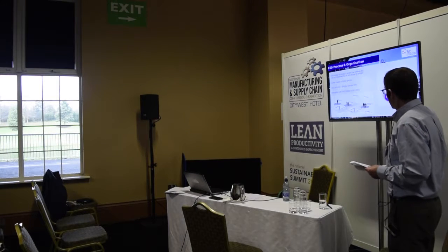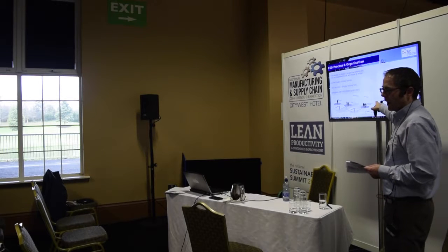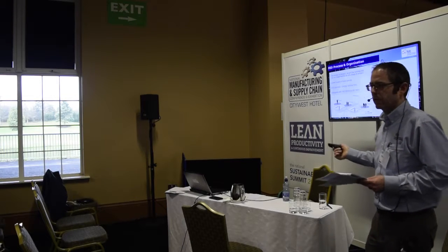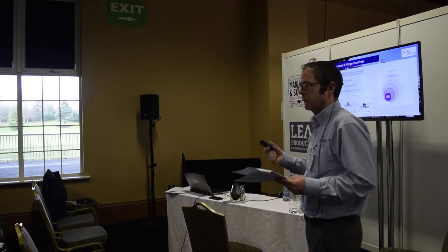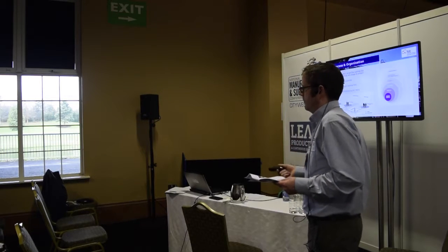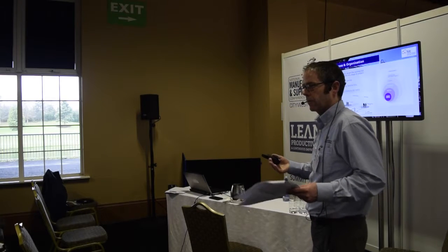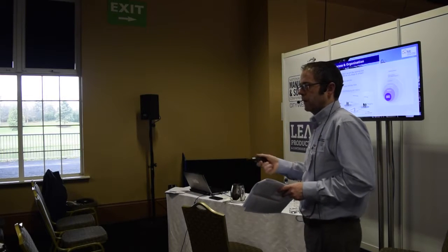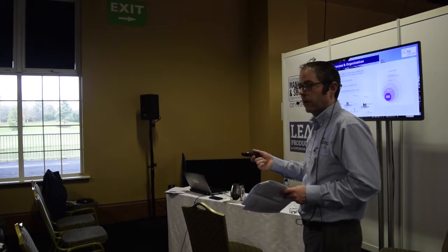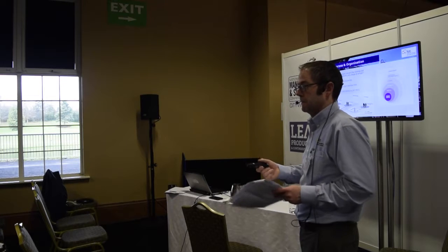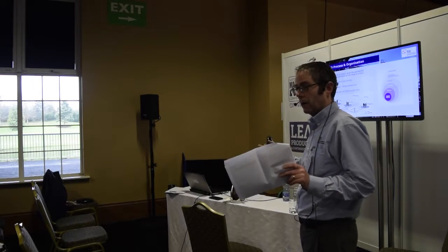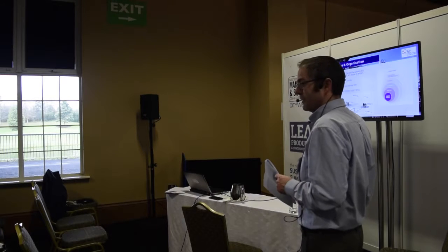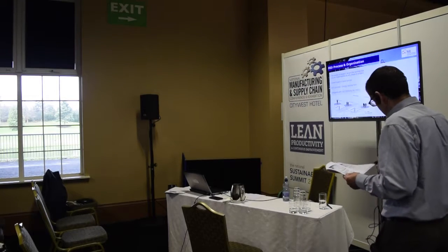The energy efficient design process is very clear that you start looking at the energy service first, and then you build up these different layers. And just to give an example, the energy service is something like a temperature, or a requirement for lighting, or air changes in a pharmaceutical facility. So before you say, okay, we're going to optimize the HVAC system, we're going to say, do we actually need 16 air changes an hour? Could we get away with 8? Could we get away with 5? And if you can do that, then you've made massive saving already. So that's in a nutshell. I could talk in detail about this, but I won't get into the detail of it.